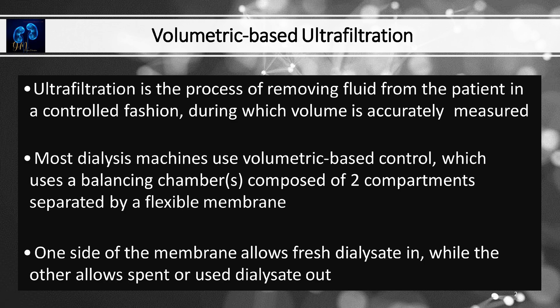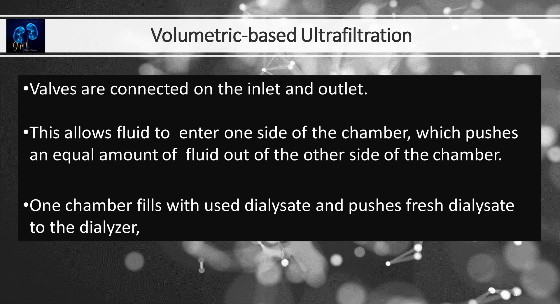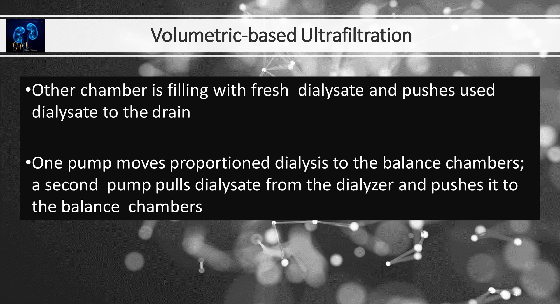It's not a semipermeable membrane — it's just a flexible membrane. One side of the membrane allows fresh dialysate in while the other allows used dialysate out. Valves are connected on the inlet and outlet of the chambers, allowing fluid to enter one side and push an equal amount out the other. One chamber fills with used dialysate and pushes fresh dialysate to the dialyzer; the other fills with fresh dialysate and pushes used dialysate to the drain.